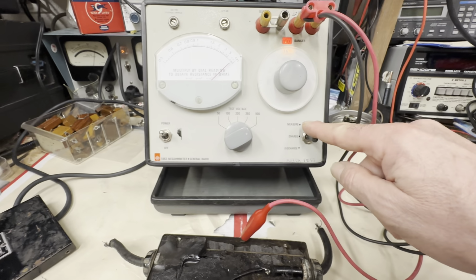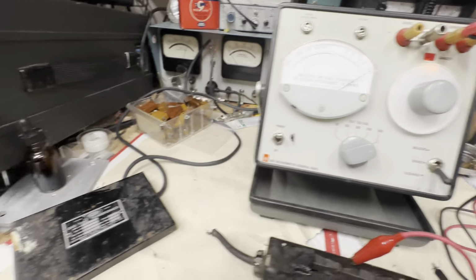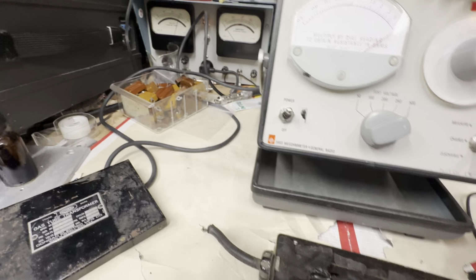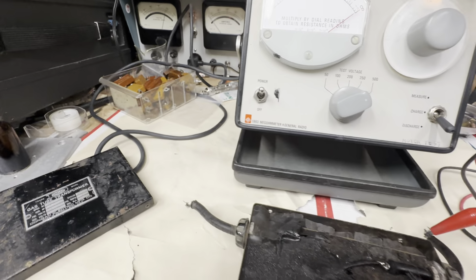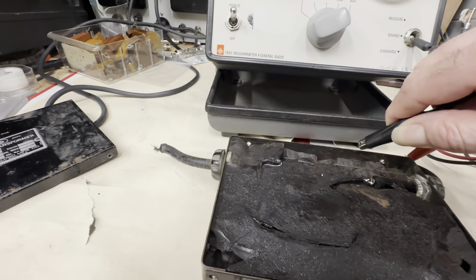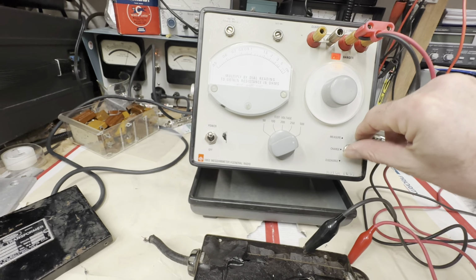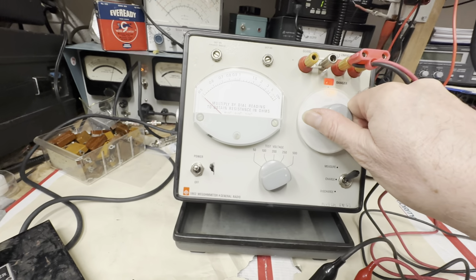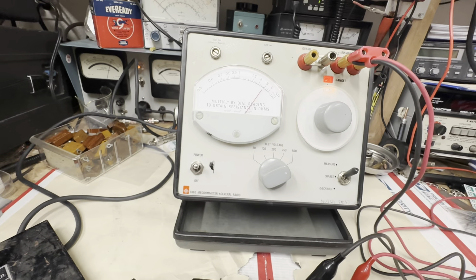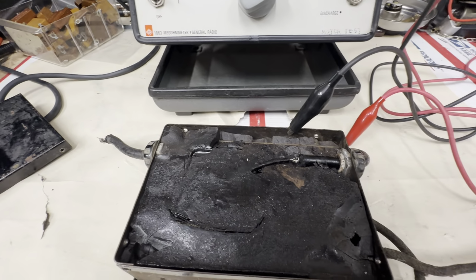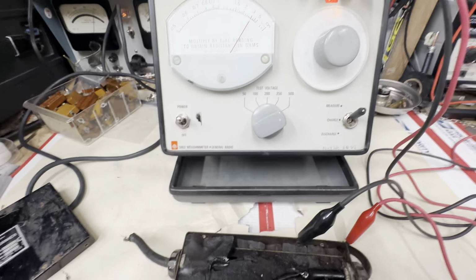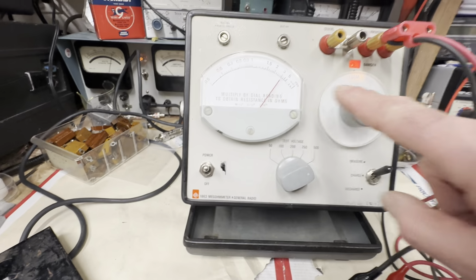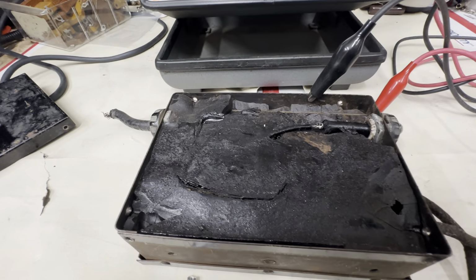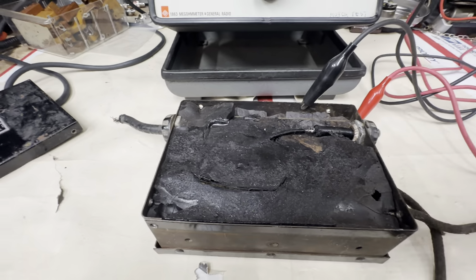Let's switch back to safety, shut that off. And now let's go to the 3,500 volt tap. And we're going to go to ground. And uh-oh, we have a problem, Houston. Let's go look at this. If we look at this, this is probably the worst case scenario right here. You actually have 300 megohms to ground leakage on the high voltage side. So this is where it's likely to fail.